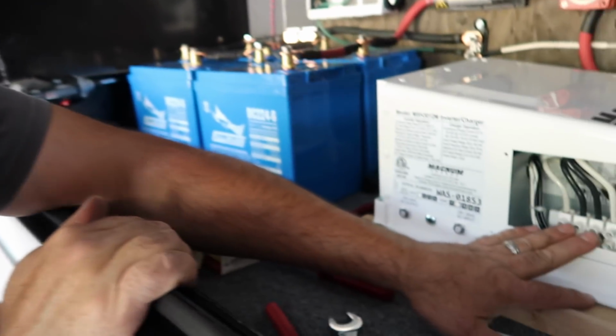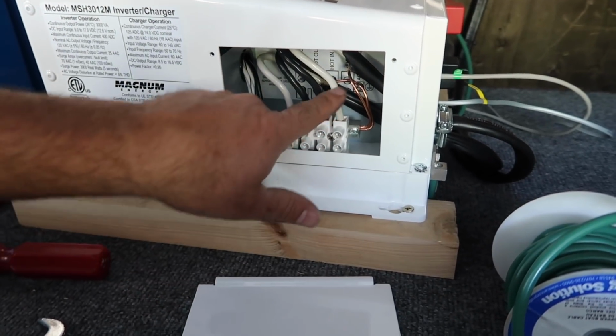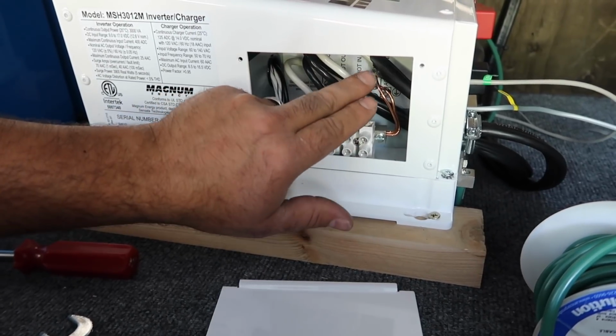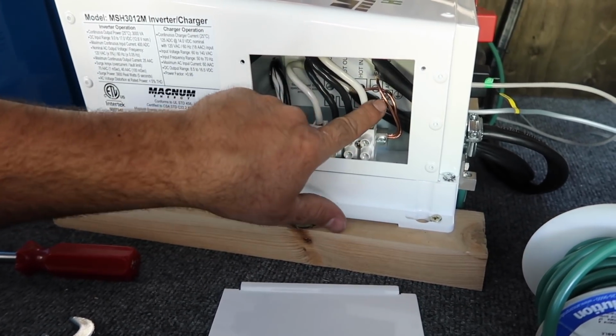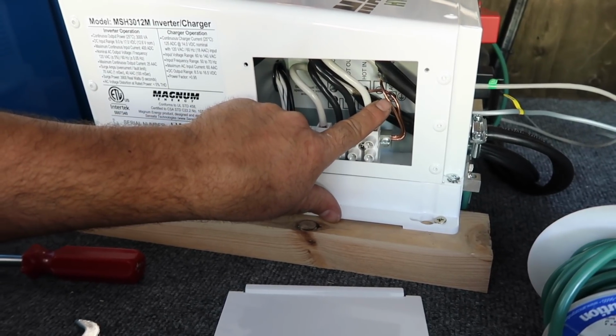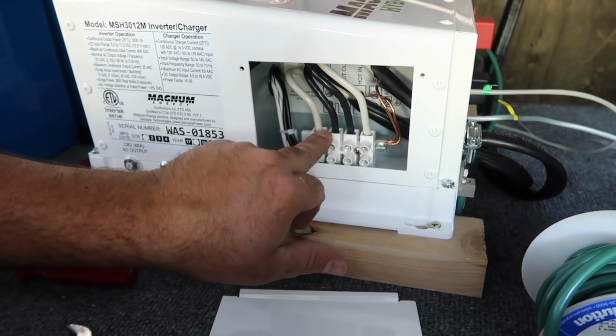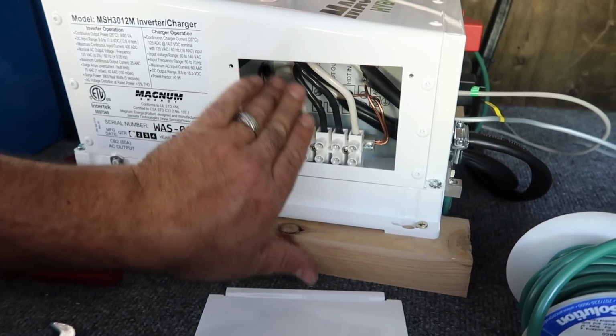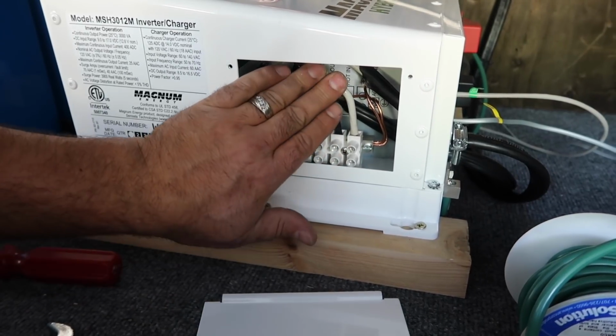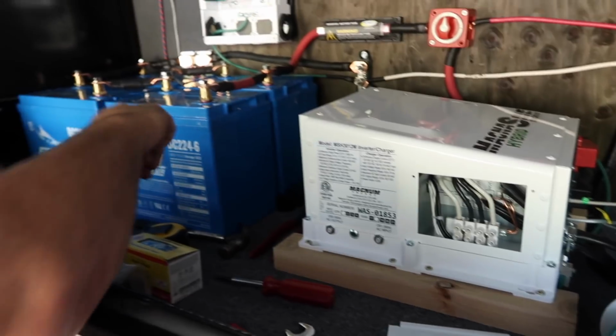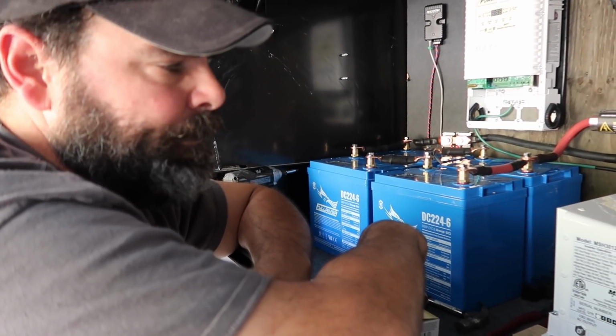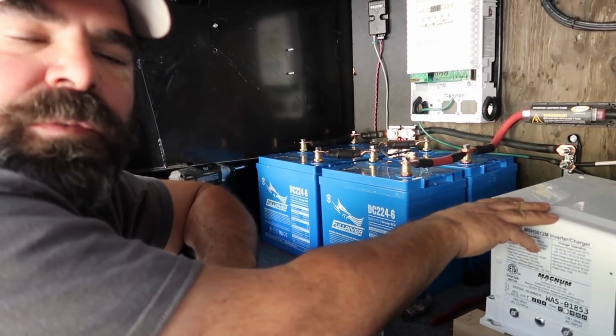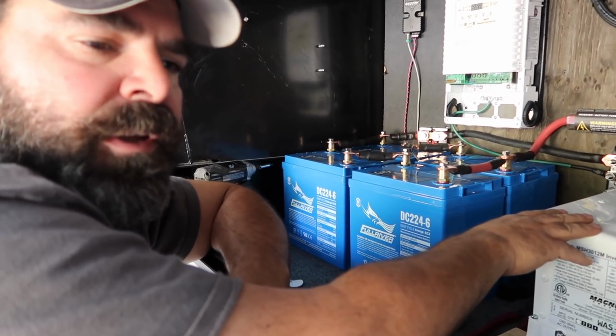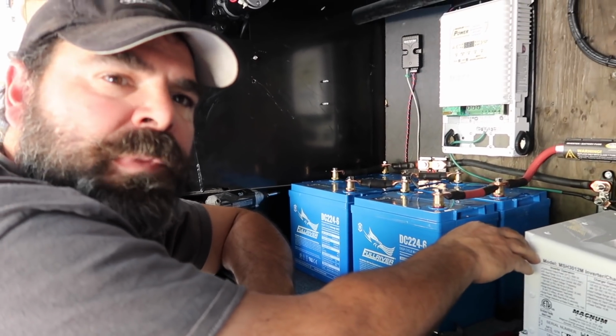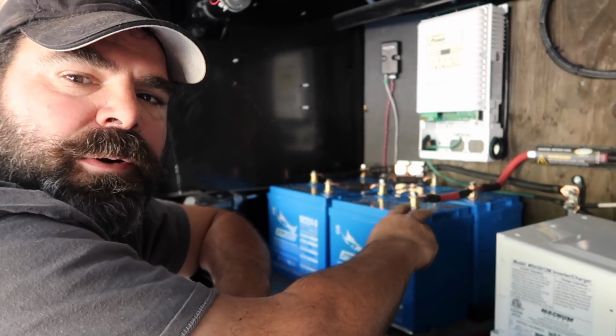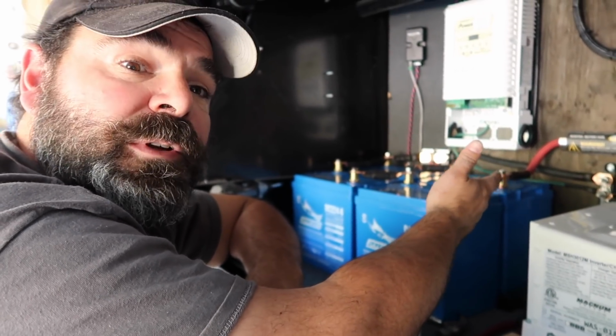Alright, you can see I've also wired in the inverter. This is the 6-2 wire. One side, looks like the hot side, comes in from the main circuit breaker board, and then it jumps over to the sub panel. So this side over here goes out to the sub panel. So this is 6-2 wiring going to and from, and it'll support the 50 amp load without a problem. The inverter also has a transfer switch in it, a 50 amp transfer switch, so when it senses that there's shore power, it'll grab the shore power versus inverting battery power. That's the purpose of a transfer switch.